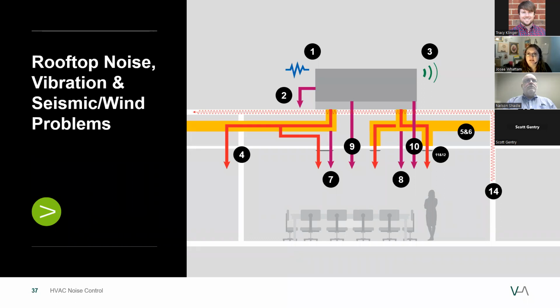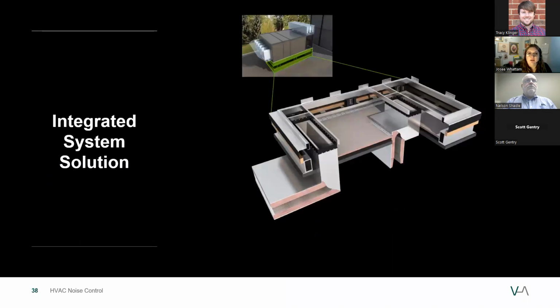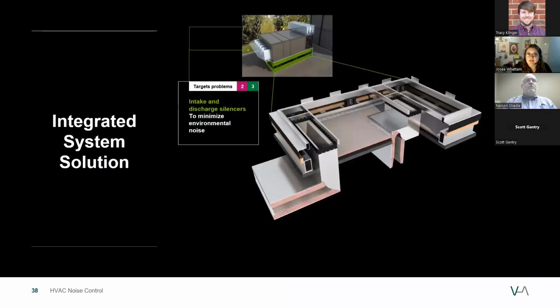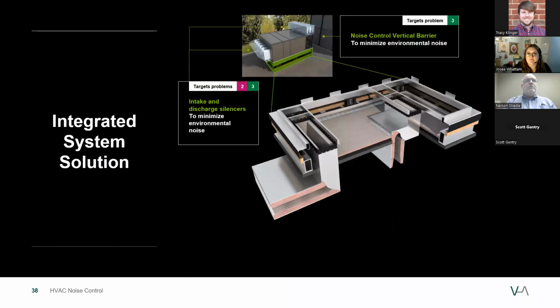After we complete an analysis on such a project to determine the noise sources, the aerodynamic conditions, and the project-specific requirements, we then can provide a specific integrated solution for this project. This would include inlet and discharge silencers and vertical barriers to minimize environmental noise. Typical RTUs have little static pressure to spare for silencing noise radiated to property lines.